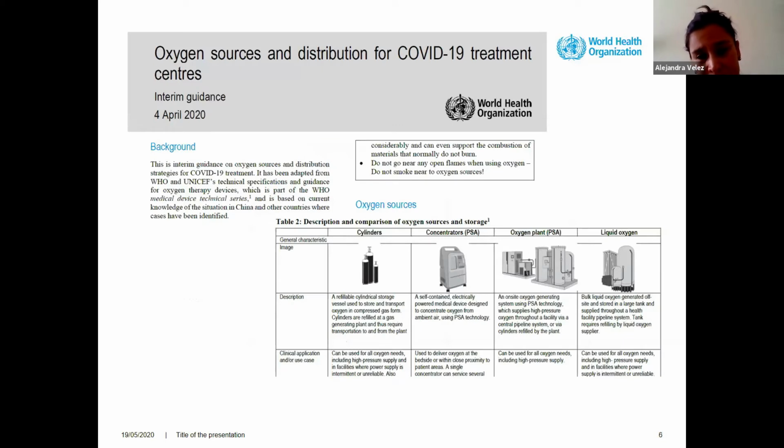Also, before going deeper into the ventilation, I wanted to mention this publication because this is basically a main component before procuring or assessing the ventilators. We need to know which kind of source of oxygen we have in our health facility. So for the time being, we have compiled this publication that is based on previous work done with WHO and UNICEF. And together with this, we have also developed the technical specifications for the PSA plants, which are also publicly available.